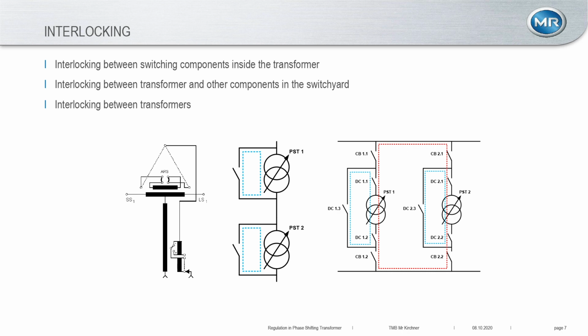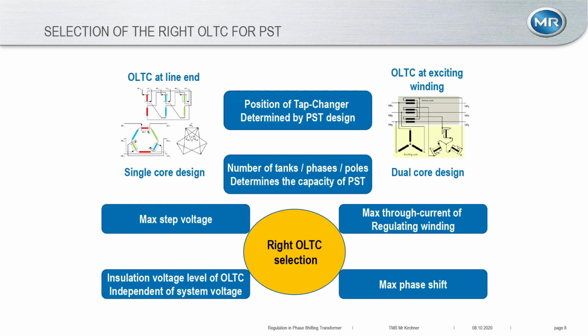And the third interlocking condition is between transformers. As I already mentioned, if you have parallel operation of transformers, you might need an interlocking between these two units, so that this difference in steps does not get too huge, so that you don't generate too big circulating currents. This is to consider, especially for OEMs here.